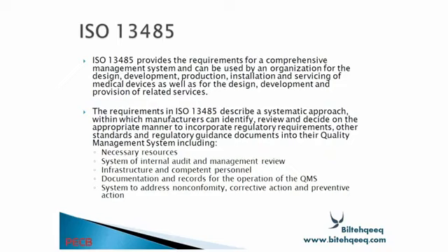Basically, ISO 13485 provides the requirements for a comprehensive management system and can be used by an organization for the design, development, production, installation, and servicing of medical devices, as well as for the design, development, and provision of related services. The requirements of ISO 13485 describe a systematic approach within which a manufacturer can identify, review, and decide on the appropriate manner to incorporate regulatory requirements, other standards, and regulatory guidance documents into the quality management system.